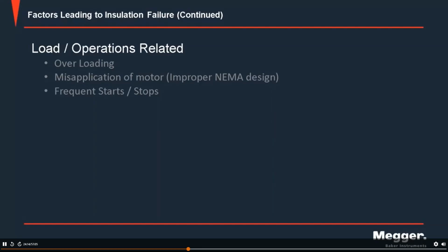There are limitations. EASA has a nice book that they hand out that includes a table that tells you how often you can start a motor, how much time you should wait between starts, and quite oftentimes we're either overriding protections or there's no protections in place to limit that, and operations might exceed the start-stop recommendations, and of course wear out the insulation prematurely.